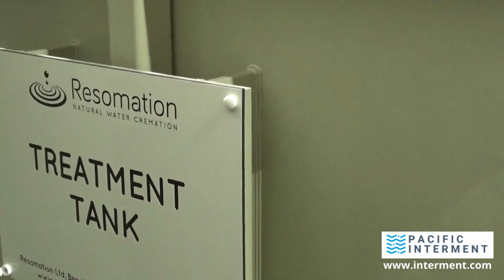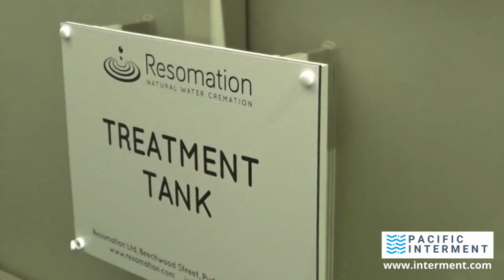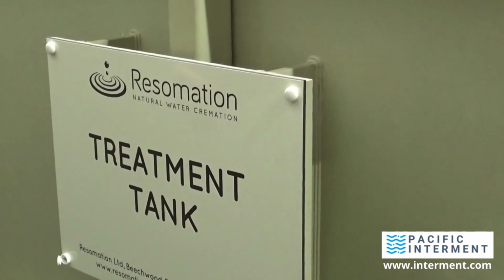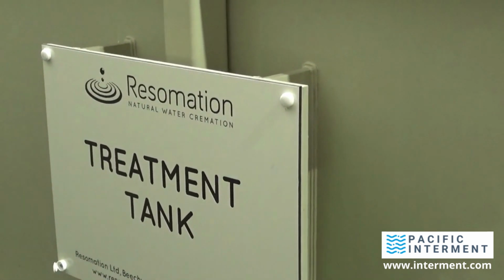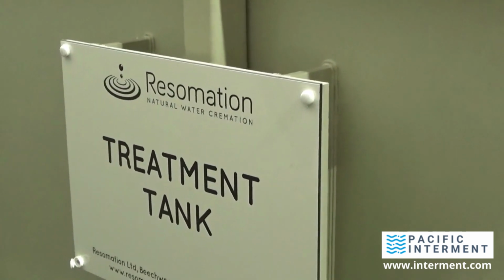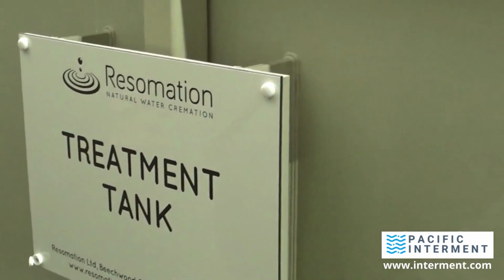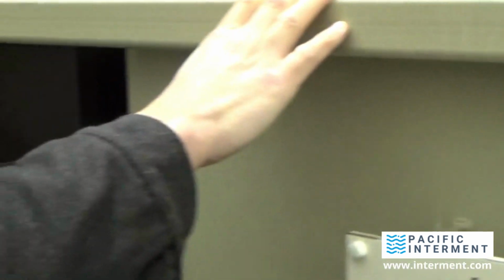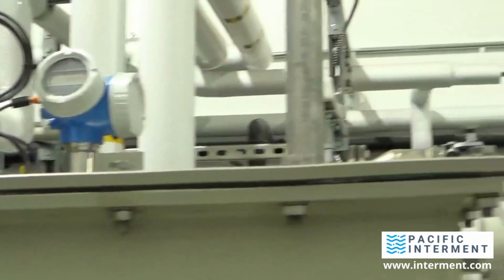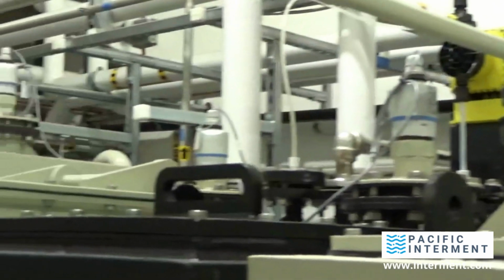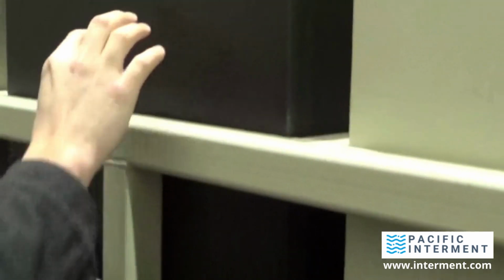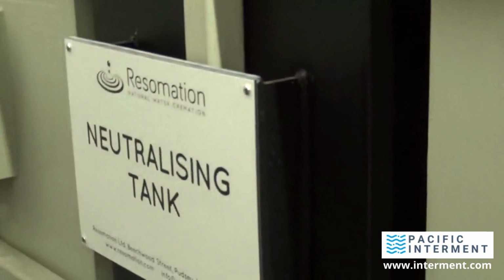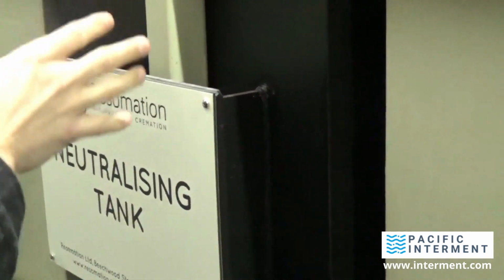The effluent is piped over to this treatment tank where it can be neutralized to meet city or state guidelines and atmospherically cool down, so it's safe to go to drain or container. Being that the system comes out at about a 12.3 pH level, most municipalities want it under 10. So we store a little bit of acid to help neutralize that. It's important to note we never use that acid to actually break a person down, only to treat the effluent that's left.